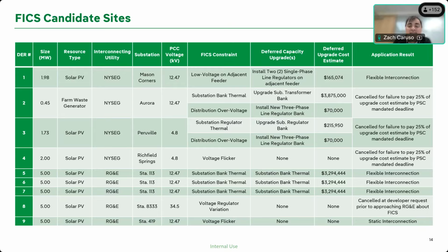Mainly, we learned that for voltage issues, which we targeted with our first DER and with some of these subsequent DERs, the cost of the mitigations generally doesn't justify and isn't commensurate with the value gained from the flexible interconnection. And sometimes those constraints can actually require a significant amount of curtailment to control the voltage sufficiently to stay within our ANSI limits. That created a lot of challenges when it came to implementing voltage-based flexible interconnection. And so that's why we have moved forward with thermal approaches for the most part, as with Spencerport, which is on station 113 up here, that was a substation bank thermal constraint.